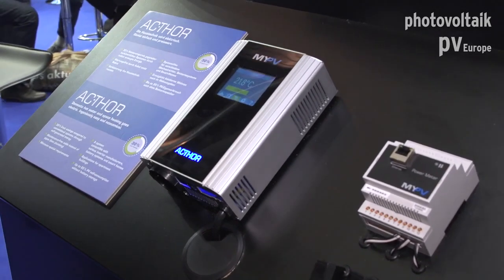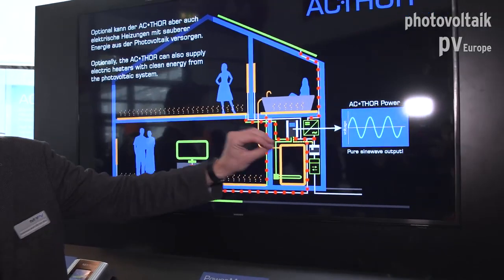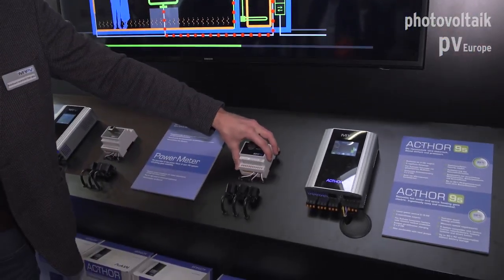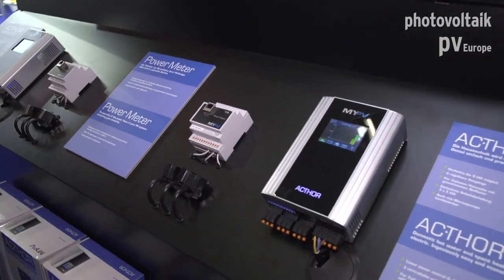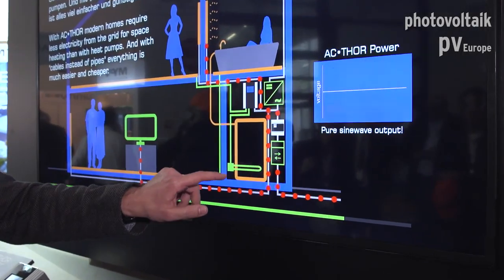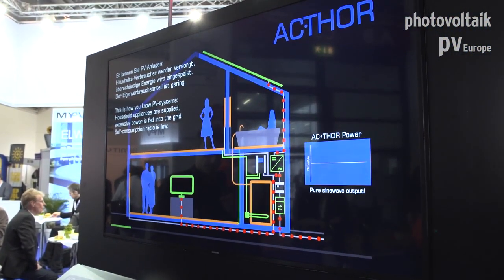The excess power changes constantly — PV production varies and appliances switch on and off, so the balance at the feed-in point changes permanently. We meter at the feed-in point with our power meter to detect how much excess power is available across all three phases. Via Ethernet, the power meter sends the excess power information to the AC-THOR power manager, which sets its power accordingly to avoid both feed-in to and import from the grid. This control loop runs once per second, very fast and very accurate.